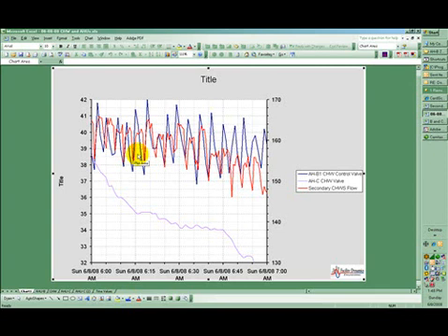so we may need to resize the valve or change the port if that's possible. It could be that if we lower the differential pressure on the system that we're controlling, that will help mitigate this issue, but I'm not sure we can do that because I think, if I'm not mistaken, Gary and Ron have already tested and the pressure we're holding is pretty much what we need to deliver the flow to the downstairs area. But I'm not positive about that. So one step in the process, if we prove it's the valve, may be to sneak the set point down on the differential pressure we're holding up in the penthouse. So I'd like to propose we do that test and see where it takes us.